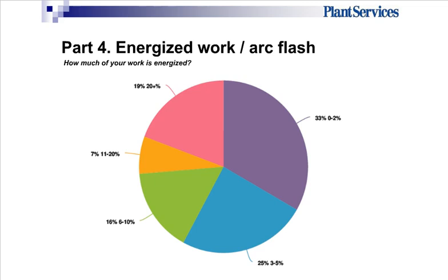Corey and I were talking before this about what we're seeing, and Corey maybe can step in and explain some of the thoughts behind the numbers that you're seeing with this question and with the question on IR windows and IR tools. Sure. Hello, everyone. When you're trying to look for a problem, especially with loose connections inside an active panel, you want to stay away from the loaded cannon and away from the arc flash zone.